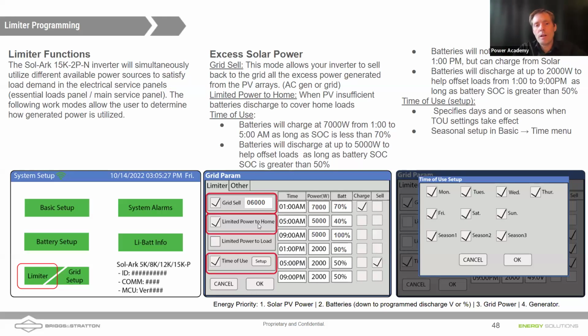Limited power to home is the ability of the inverter to limit how much power you're pulling from the grid at any instant in time. So there's a setting in the general settings where I can limit how much overall power is pulled from the grid. For example, if the home is using 10 kilowatts, but I've got limited power set to the home at 5 kilowatts, then the excess power would be supplied by the batteries, right, if solar is not available. And so we can use this setting to limit how much overall power comes to the home.